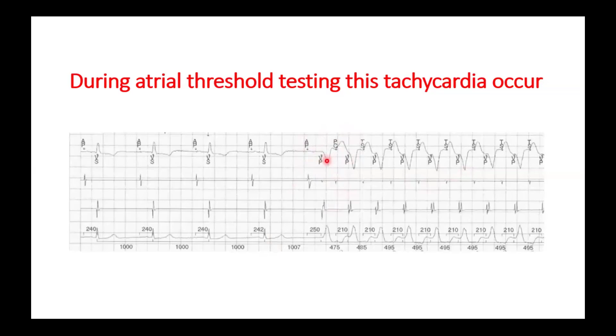Here the device considered a PVC, retrograde conduction, which starts the PMT. What happened here is that the atrium didn't capture, and the V pacing started a retrograde conduction. Here are the different etiologies and the mechanism by which the PMT is initiated. The most important thing is that the atrium is not depolarized. So it can be triggered by a ventricular extrasystole, a PVC, then a retrograde conduction. The atrium is not depolarized, and the retrograde P wave is sensed and PMT starts.